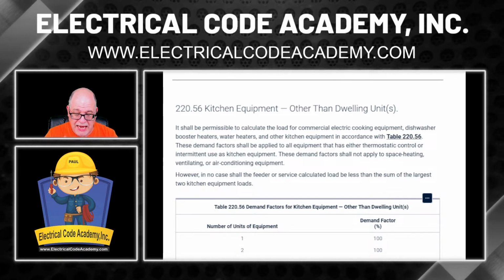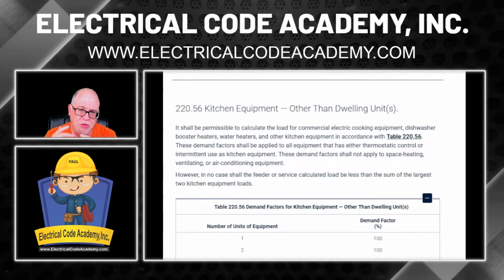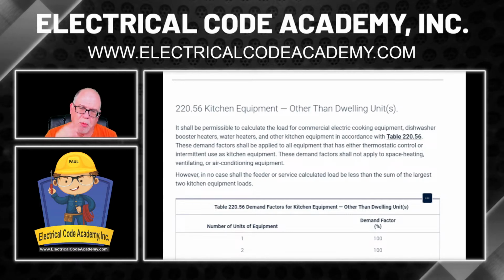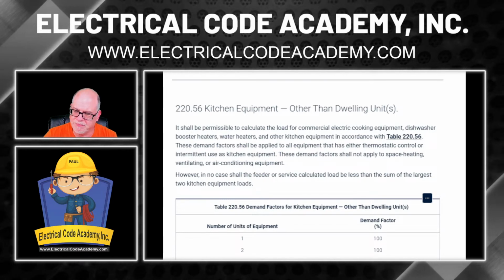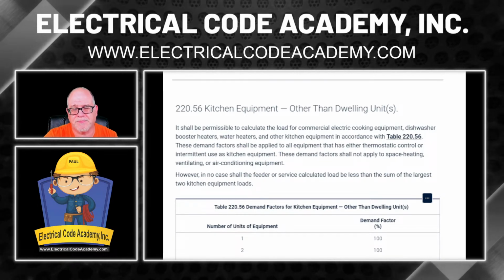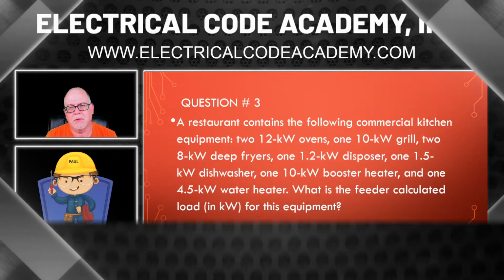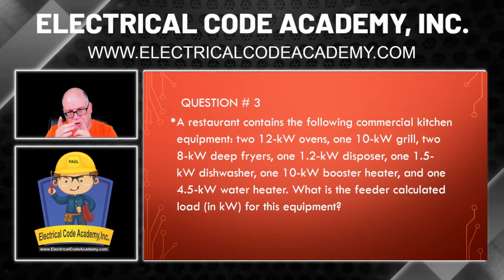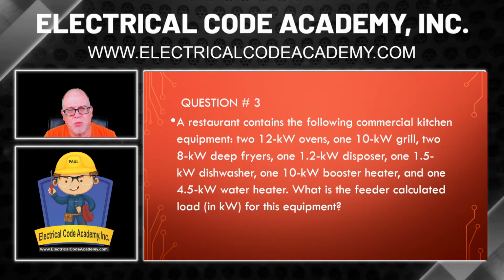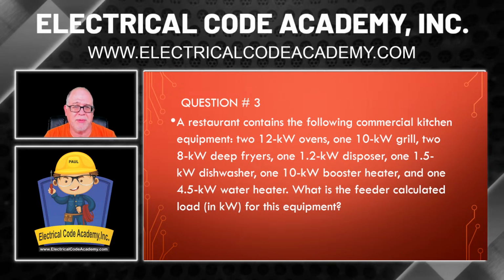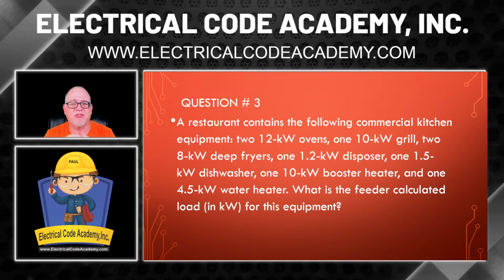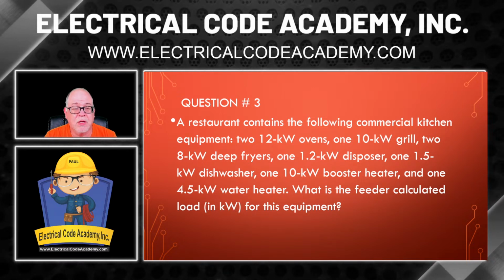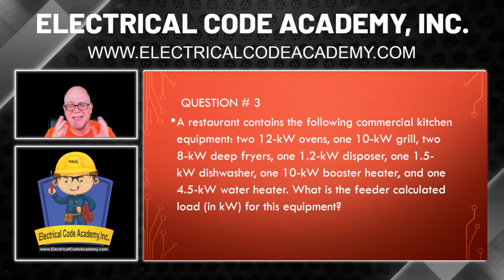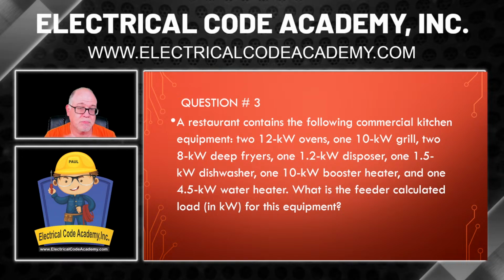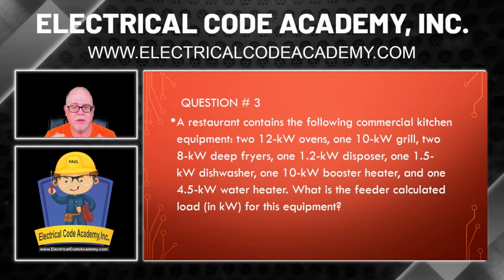Now, we added everything up, but when you looked at that list again, what were the two largest pieces of equipment? And I'll go back so you can see it. So the two 12 kW ovens were the two largest pieces of equipment here. Now together, that's 24 kW. So we already know that it can't be less than 24 kW in our equation.